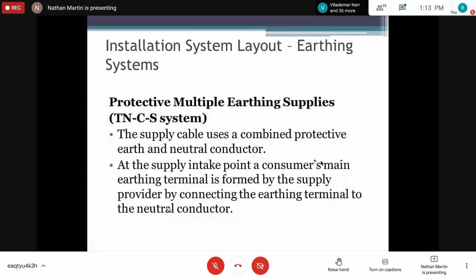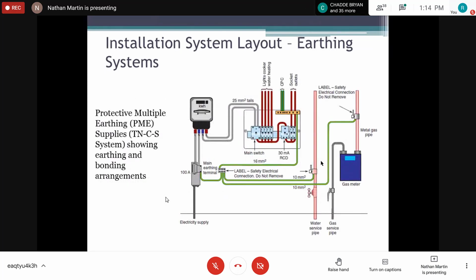The TN-C-S system, right? The supply cable uses a combined protective earth and neutral at the supply intake. So we have a combined protective earth and neutral, right? So they are combined at the supply intake point at the consumer main, right? So this is the type of system that we're talking about. So right here at the consumer main, the earth and the neutral are tied in, but no earth is provided by the supply company, or by an earthing rod. All we have to do is rely on the earth neutral that is being supplied by the company itself, right? So we don't actually drive an earth rod in this system, right? And this system is really not our system. We'll soon see what our configuration is, right?